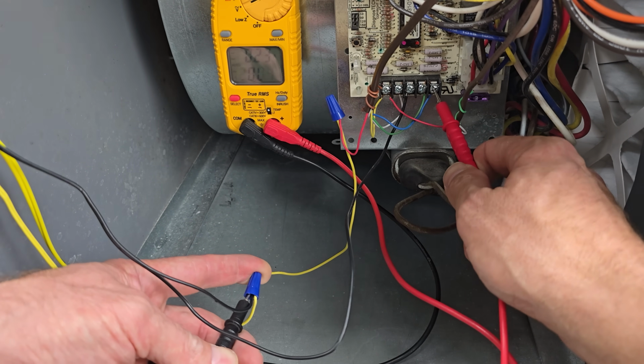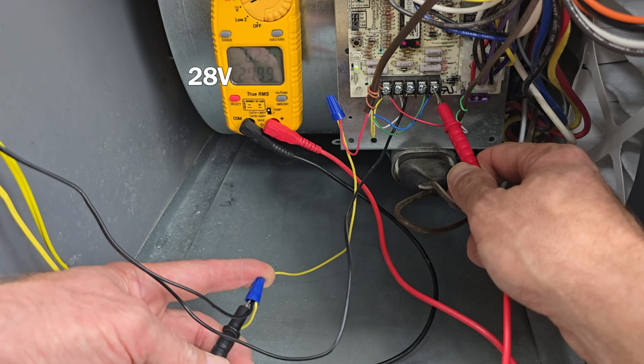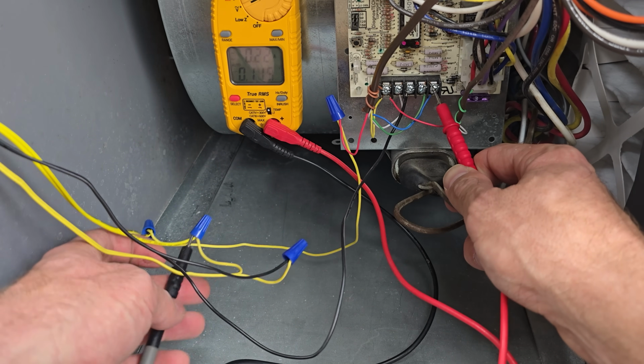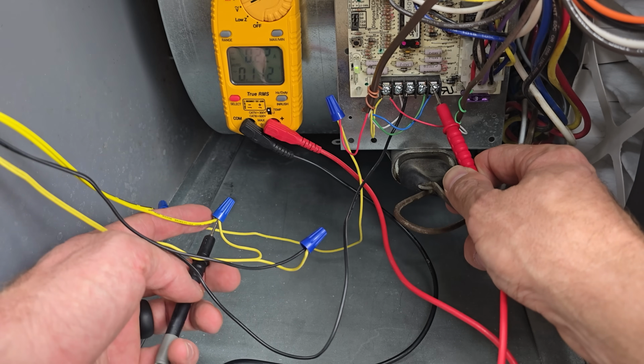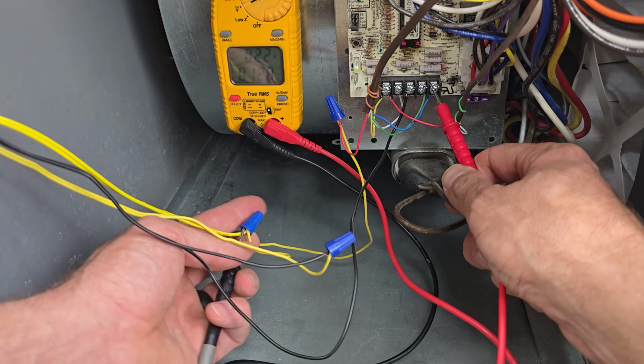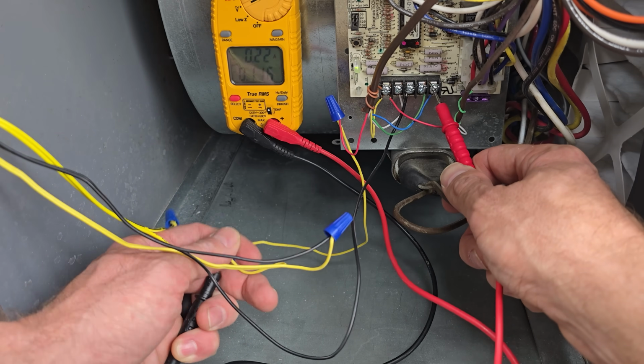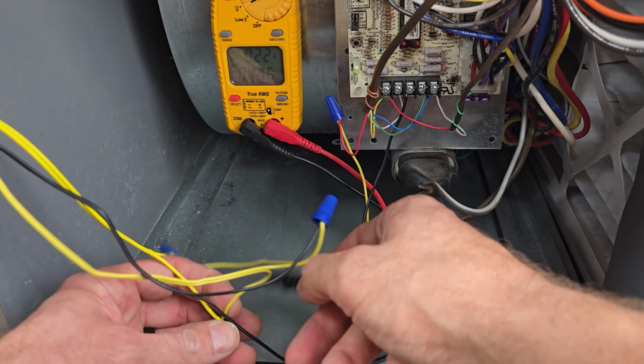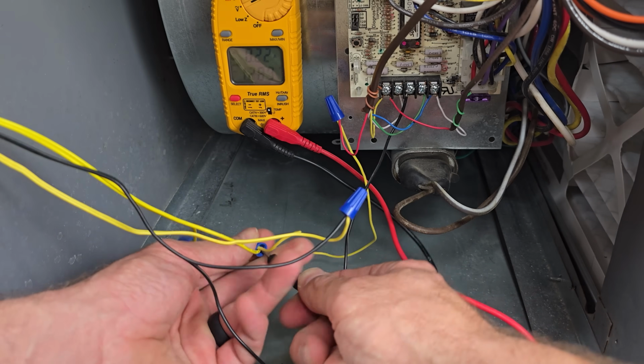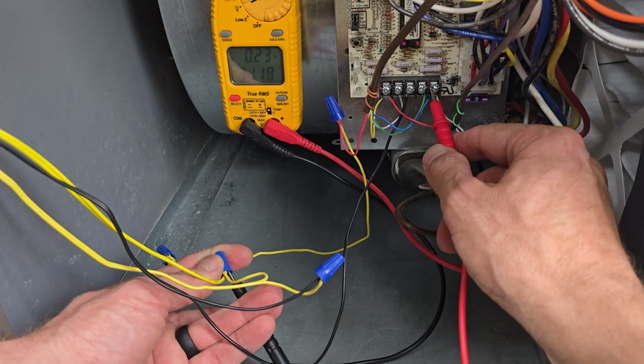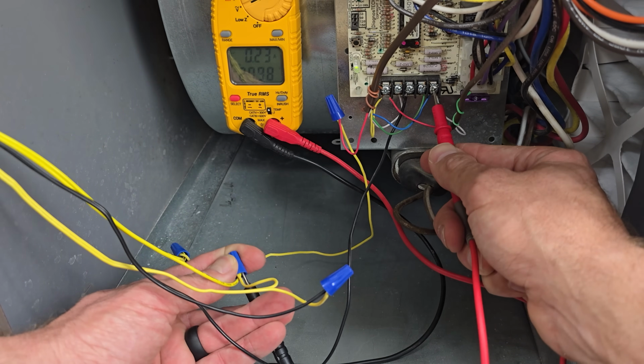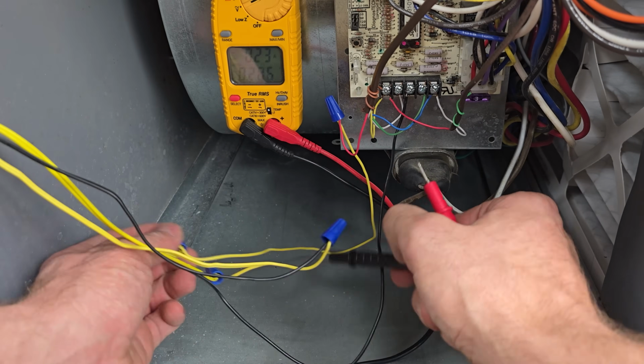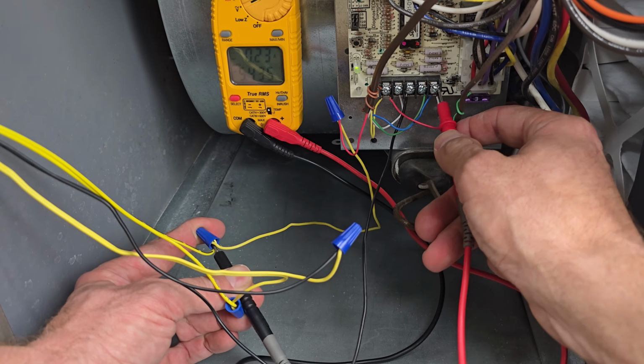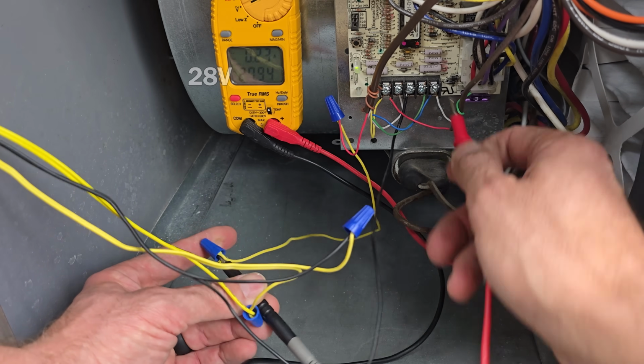Once again, if I put the probe on the common, 28 volts, 27.99, and then let's measure through this switch right here. That one's really tight. Sometimes you have to find a really good spot inside to make contact with the metal. That one's good, 28 volts there. 28 volts there. So now we should have power up at the thermostat.